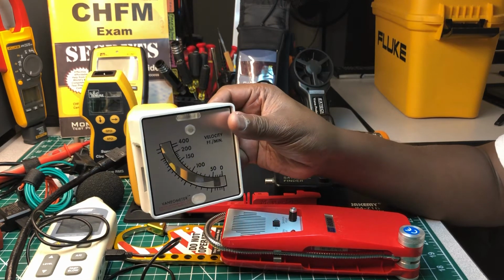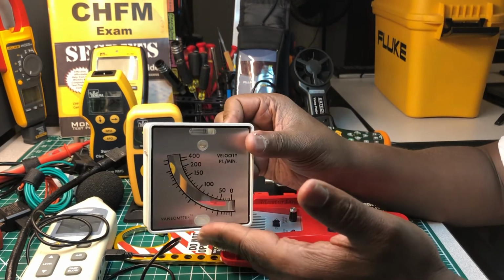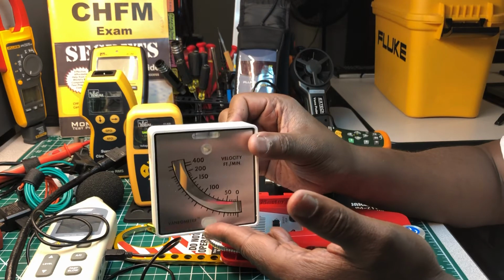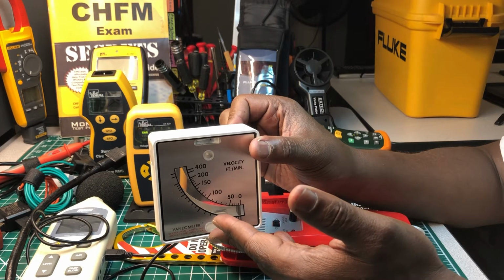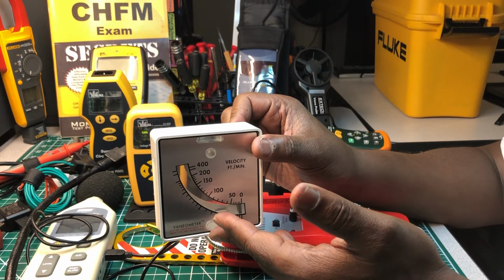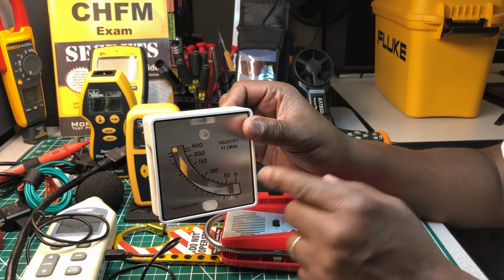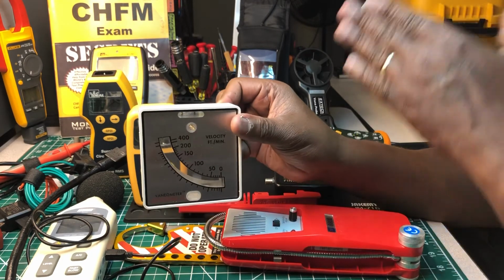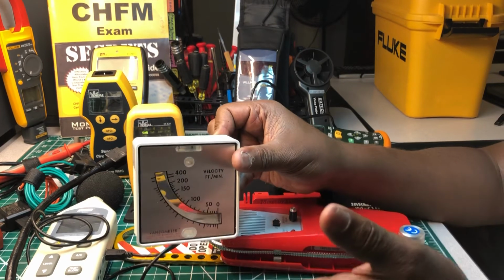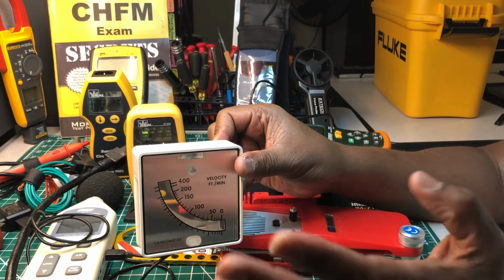feet per minute velocity. What we used to do, there's a thing called negative air and positive air inside of hospitals. We used to have to check that, like in operating rooms. They need positive air inside of an operating room to push the air out, not to bring anything in. Because remember, they have someone on the table, maybe getting cut wide open, having surgery. They don't want to pull air inside that room because you're pulling germs inside that room. So they need air to be pushed out of that room.